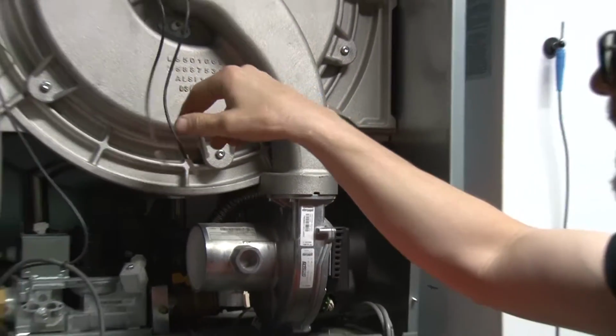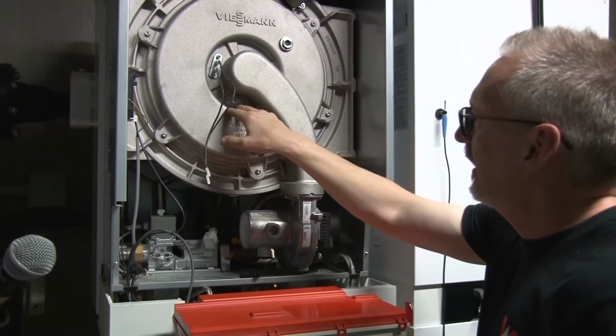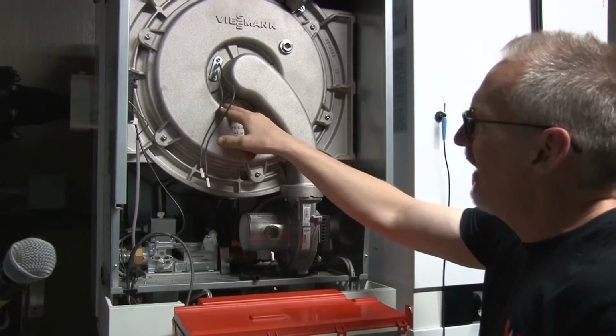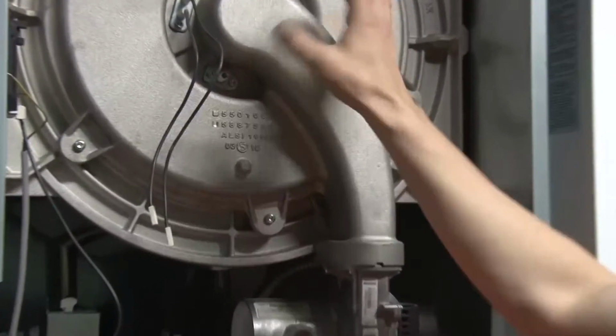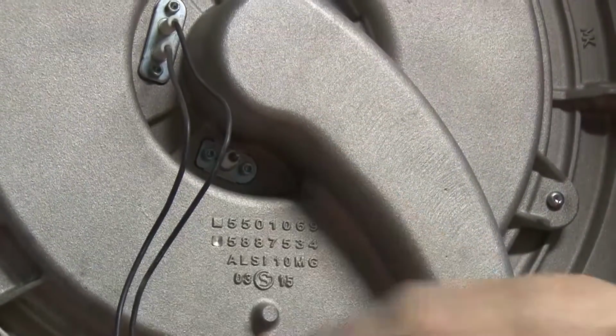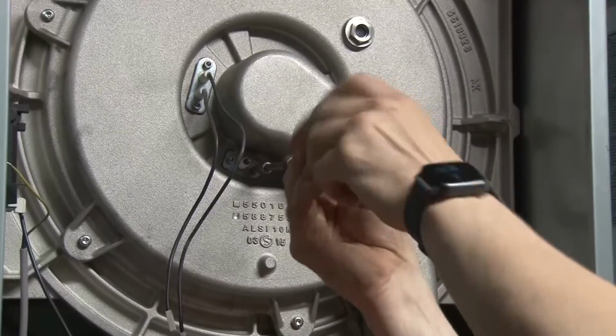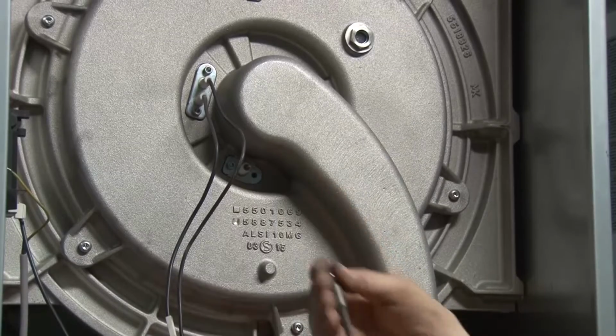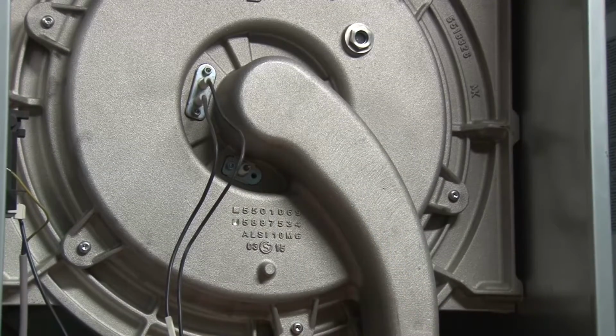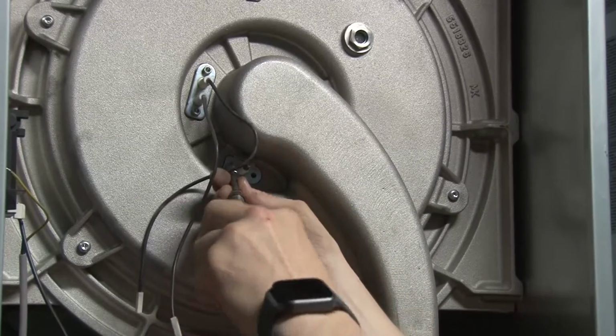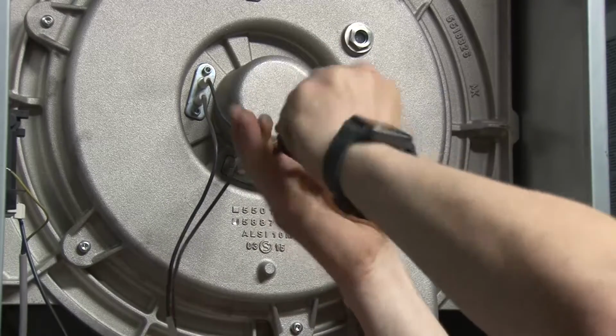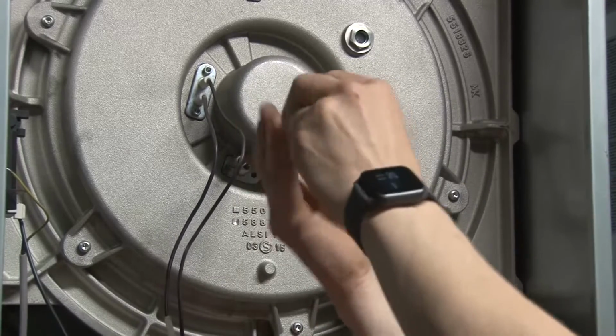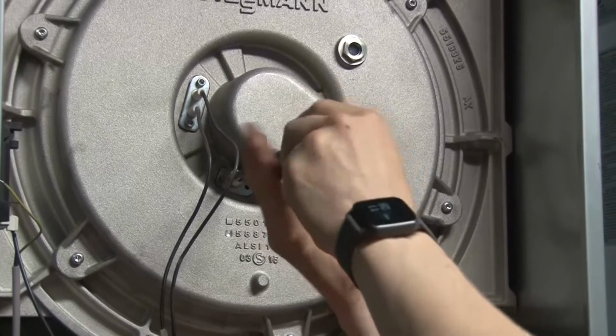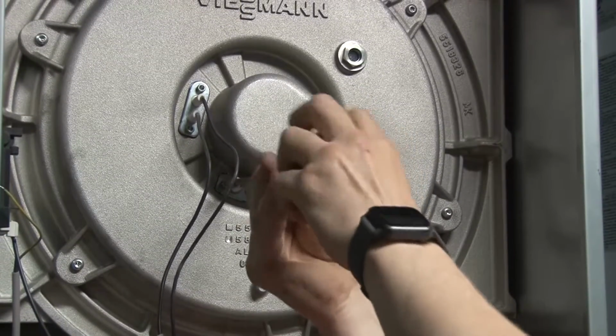All right, so before I unplug everything here, I'm going to remove the electrodes. I find them easier to remove when I have the burner still in place, just to inspect them. This is the ionization electrode, and ionization is responsible for flame proving. It's a safety in the boiler to make sure that when that boiler fires, there is a feedback in microamp DC.